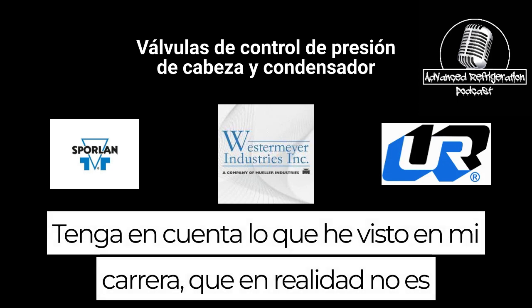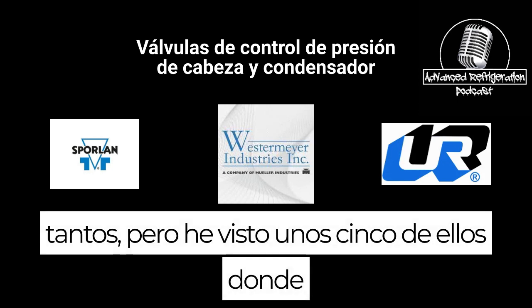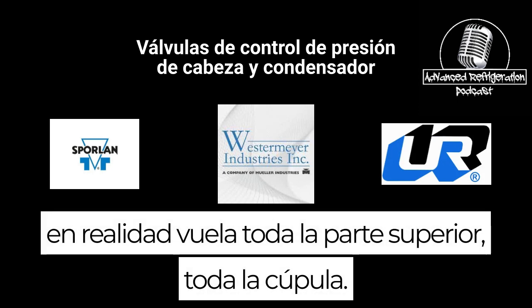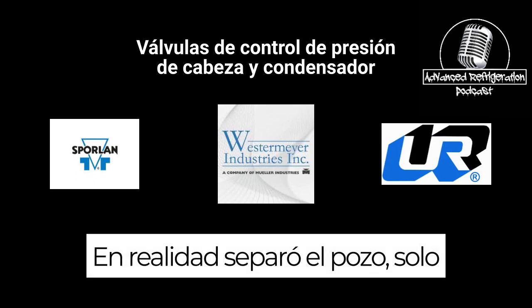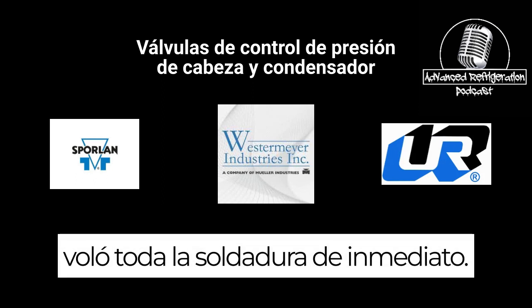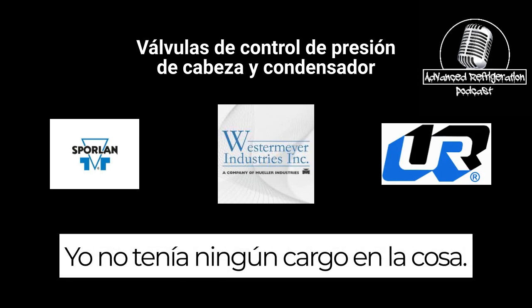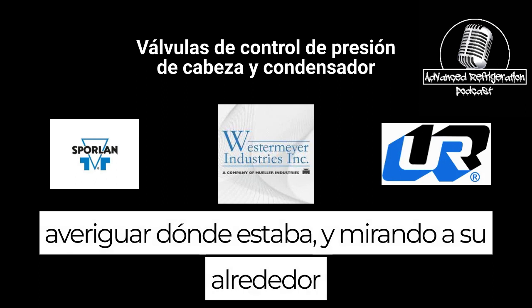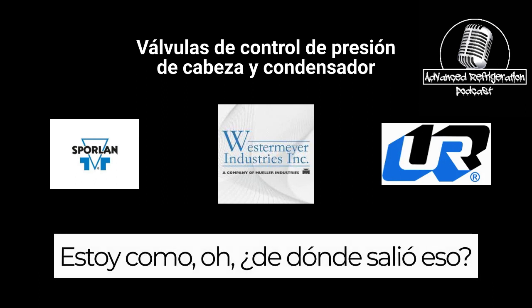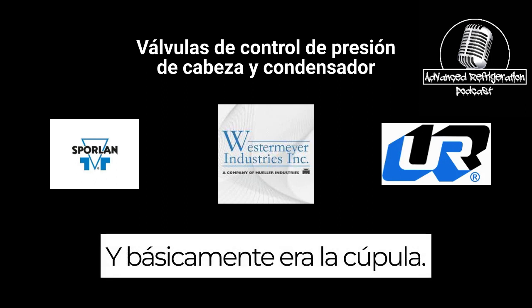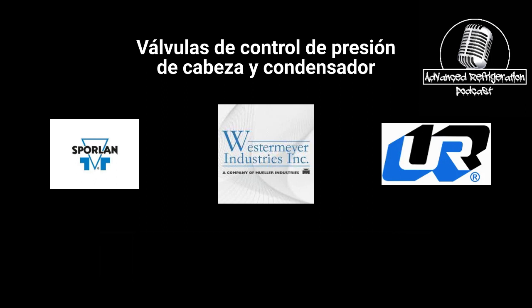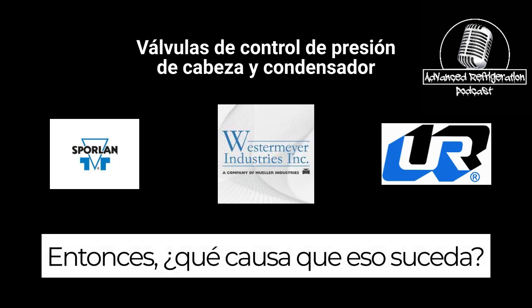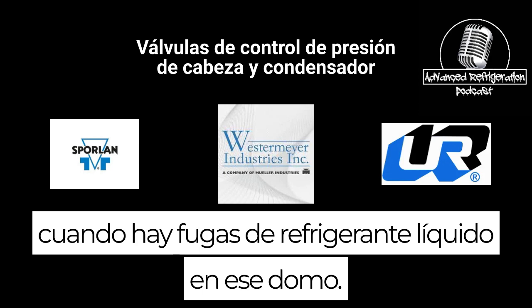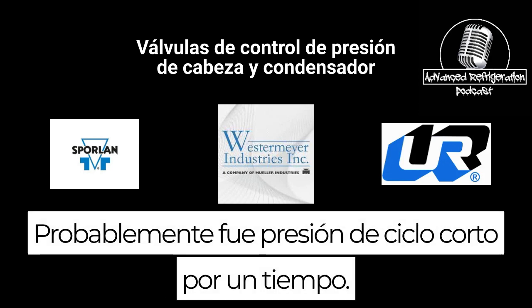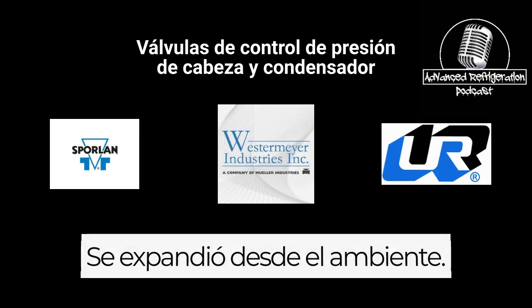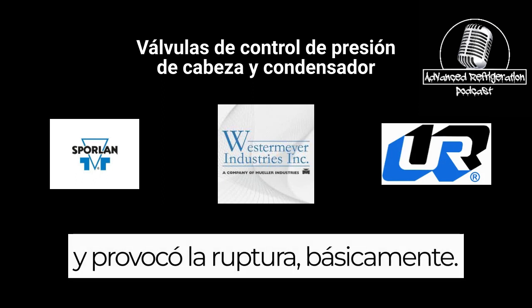I've seen in my career, which isn't really that many years, about five of them where it actually blows the whole entire top, the whole dome. It actually separated the weld. It just blew the whole weld right off, and there were pieces in the bottom. I had no charge on the thing. I started charging up with nitrogen, trying to figure out where the leak was, and looking around I see brass and a spring. I'm like, oh, where'd that come from? Basically the dome just blew its top. What causes that is liquid refrigerant leaking into that dome. It was probably short cycling on pressure for a while. It expanded enough from the ambient and caused the rupture, basically.